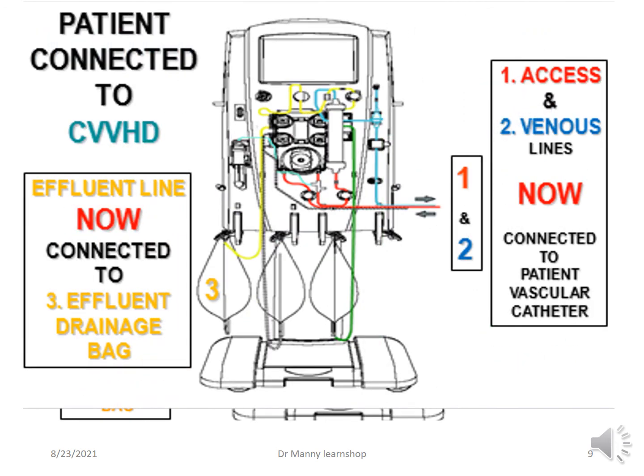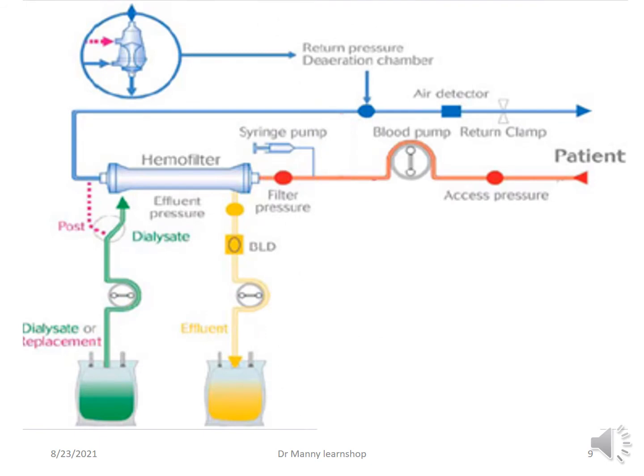Now, if we're connecting the patient, the effluent line is connected to the effluent bag again, and the access line and venous lines are now connected to the patient's vascular catheter. So what we have, patient access line connected to the filter, return line blue. However, we have the effluent bag that collects the fluid and the dialysate which delivers the fluid.